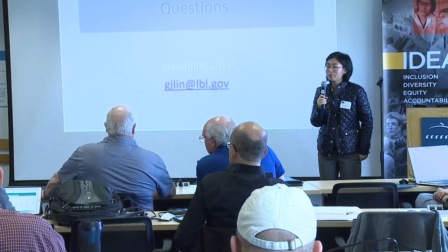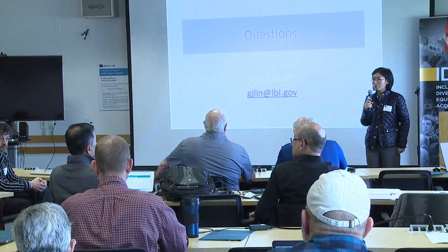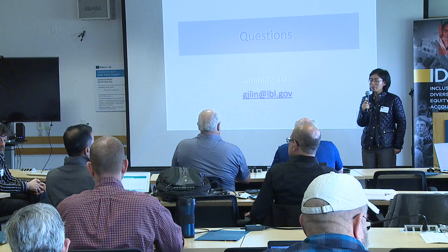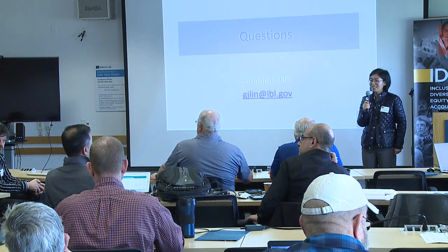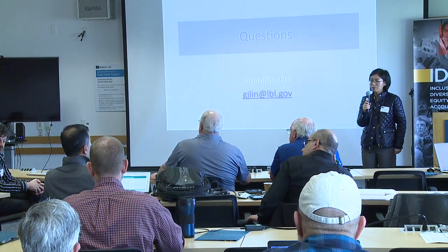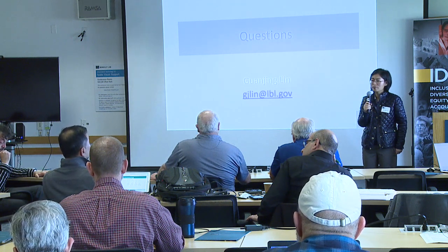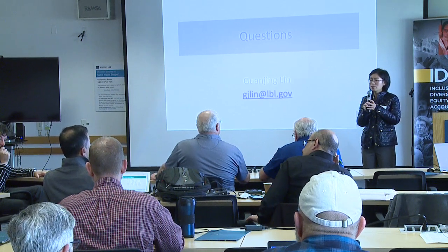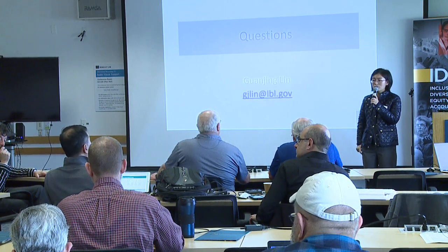Yeah, I'd like to add to that. That is a real concern because we've implemented auto fault detection, but just the one way, not the auto correction yet, using SkySpark software. And that was the concern from our end, from the facilities end, the traffic, the amount of data. We found out that vendors typically want all data.